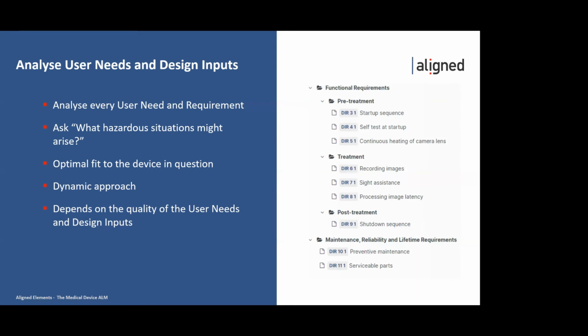And this is, of course, a dynamic approach. Each time you add a requirement or add a user need, you need to consider that one for risks, because that would then be in your process. And again, if you change a requirement, or if you change a user need, you need to reconsider your risk assessment, which is exactly what you should do. Changes made to the design should be considered from a risk perspective.